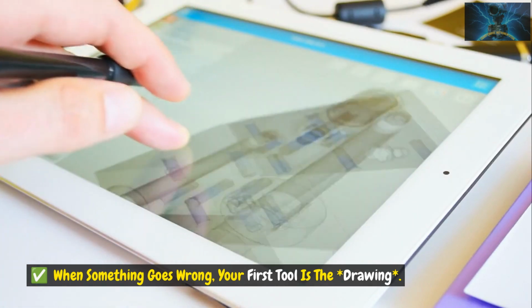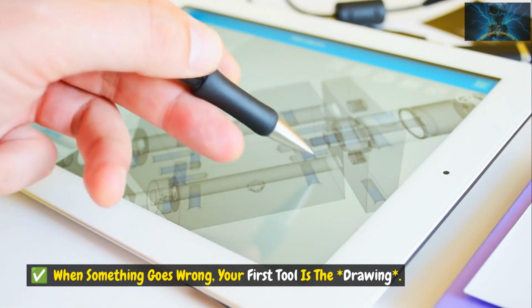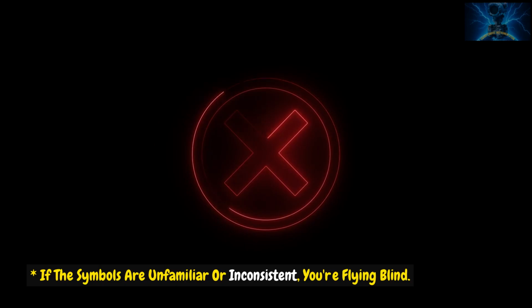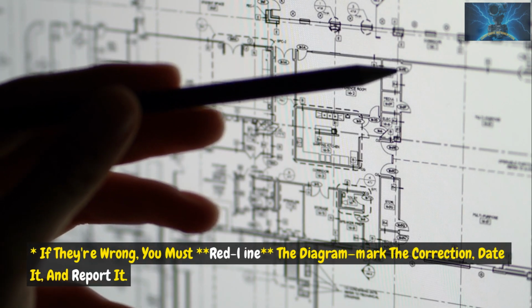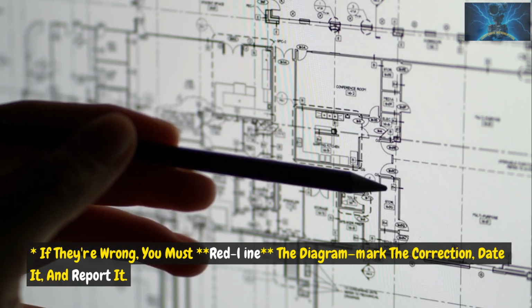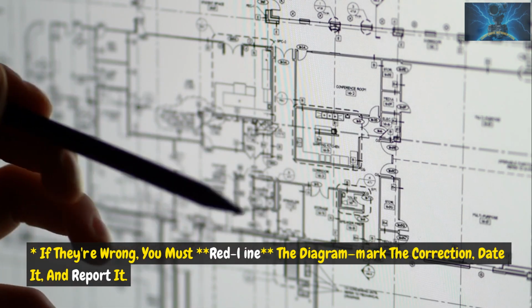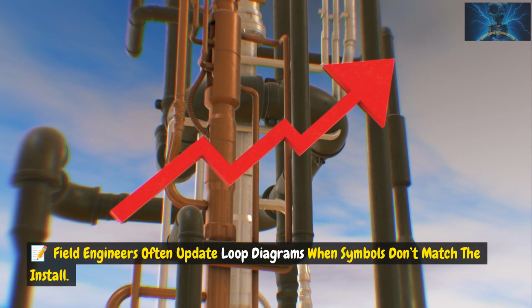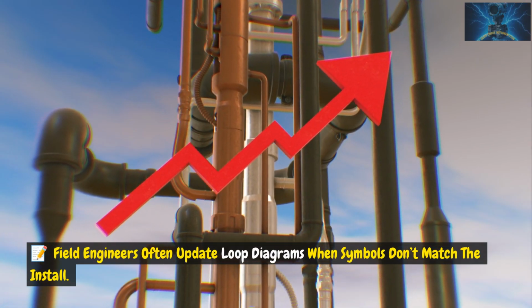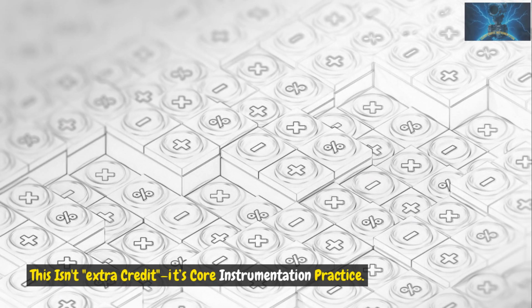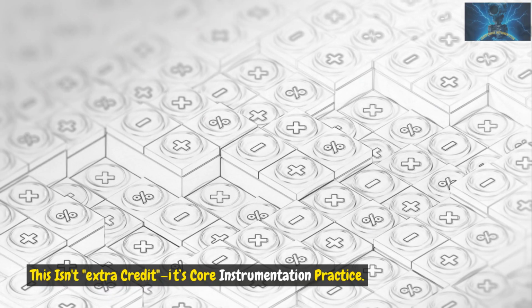When something goes wrong, your first tool is the drawing. If the symbols are unfamiliar or inconsistent, you're flying blind. If they're wrong, you must redline the diagram, mark the correction, date it, and report it. Field engineers often update loop diagrams when symbols don't match the install. This isn't extra credit, it's core instrumentation practice.